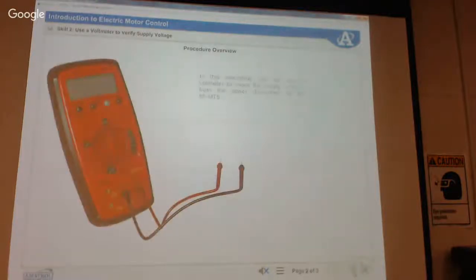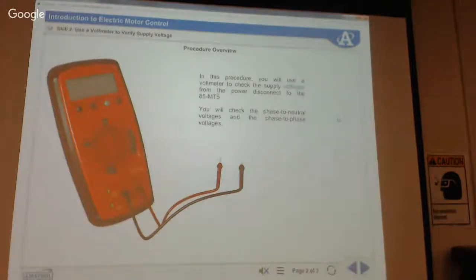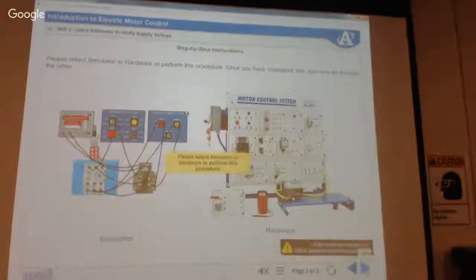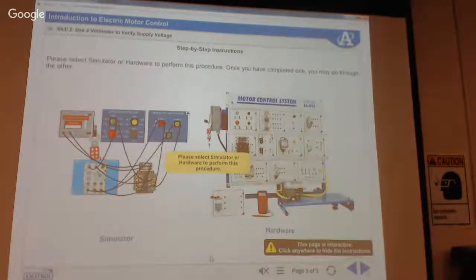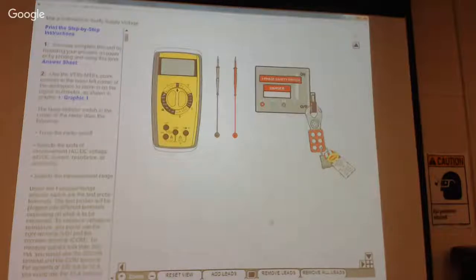Remember the transformer we went and looked at back in there? That's supplying the 3-phase to the classroom. So here we have a skill. We're going to use a voltmeter to verify supply voltage. And we have a simulator. We'll just do this on the screen up here real quick. Here in a little bit, we'll have you put on your arc flash gear, and you can do it for real since we have the equipment.